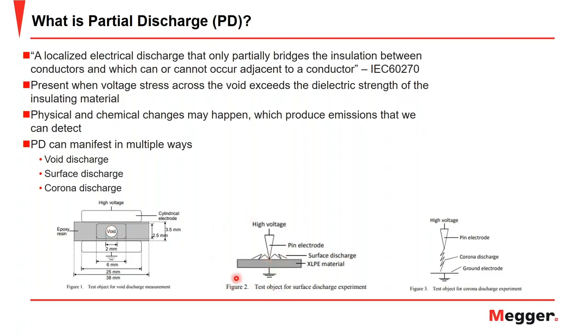Next, in the middle here, we have an example of surface discharge, where your high voltage is touching the surface of your insulating material, and due to contaminants or just a high electric field concentration, you have arcing activity between the surface of the insulating material and the high voltage potential. And this can cause PD activity on the surface here, otherwise known as surface discharging. On the right, we have an example of corona discharge, where your high voltage is not necessarily touching your ground electrode or your insulating material, but the dielectric strength of the insulating medium between them has been exceeded, and therefore breakdown is occurring between those 2 potential levels.